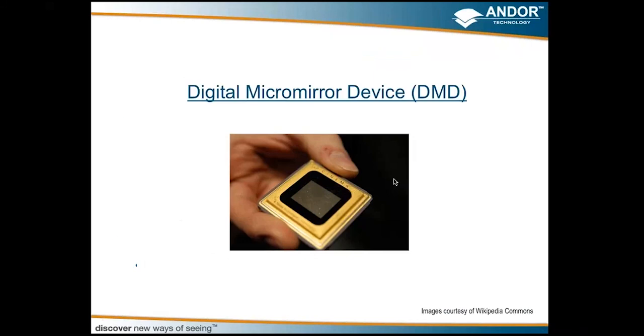So the DMD is essentially a multi-mirror array. It's hundreds of thousands to a million little mirrors, similar to what's in a projector or some other type of light projection device. These mirrors are on the scale of 10 to 20 microns, and they can switch individually very fast, on the order of microseconds.